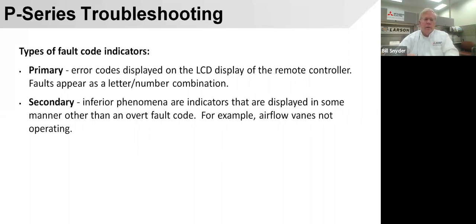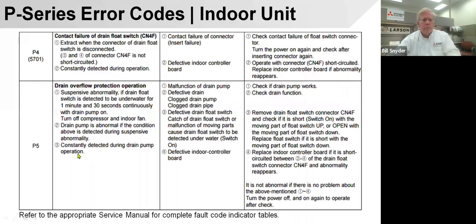So the instructions refer to inferior phenomenon, and that's Japanese speak that's been translated. And just be aware that if you see that, it's something that you're going to have to look for, listen for, smell, and it should kind of show itself, that it's something that did not throw a fault code. Like killing power to the unit won't throw the fault code. So if you blow a fuse, you're going to have to find that on your own. It won't give you a code for that.